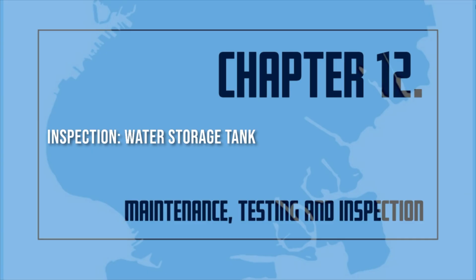Tank exterior. The exterior of the tank, supporting structure, vents, foundation, and catwalks or ladders, shall be inspected quarterly for damages and weakening. The area surrounding the tank shall be inspected quarterly to ensure it is free of combustible storage, trash, debris, brush, or material that could present a fire exposure hazard, and for any accumulation of material or ice buildup on or near parts that could result in accelerated corrosion or rot.